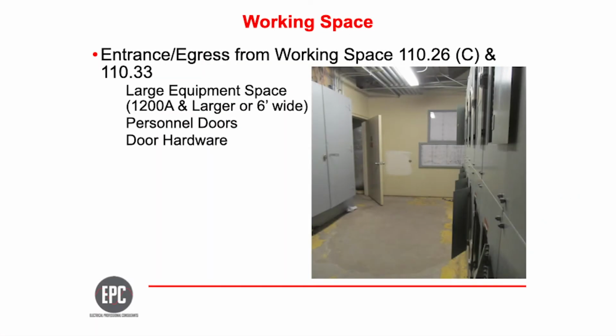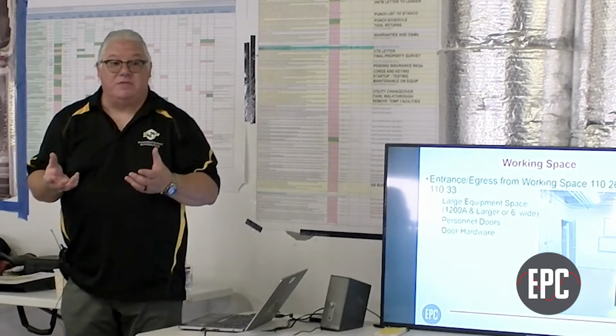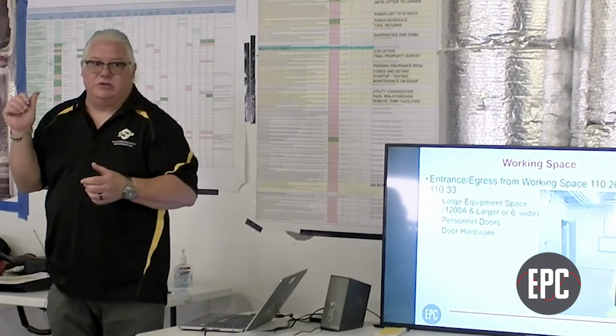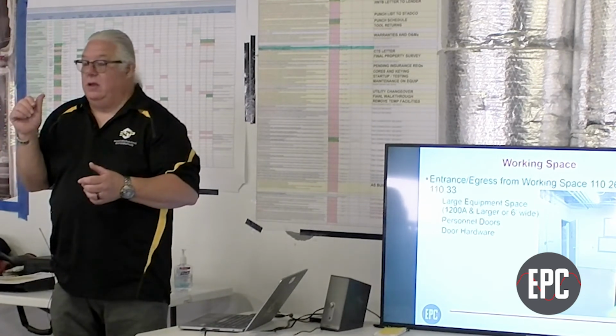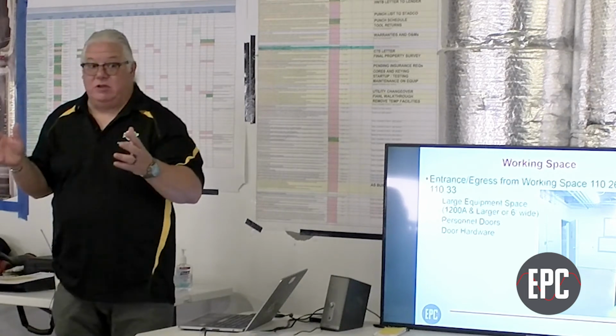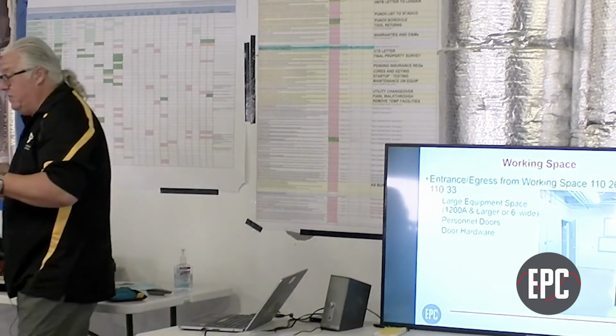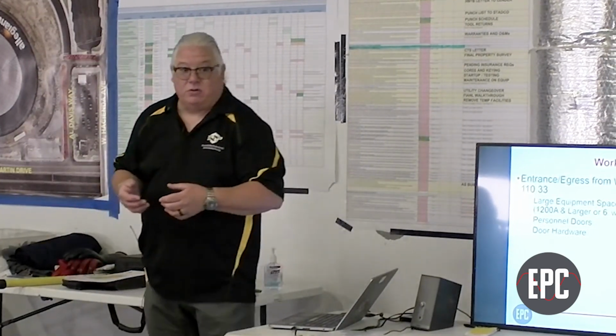We talked about egress from the room. What are some of the important things? You're in a brand new building that shouldn't have this problem, but if you're in an older facility, what are some of the important things that I want to understand about getting out of the room? Clear path, locks. I want to make sure that I can get out of the room. There's nothing worse than to walk into the electric room and hear the door shut behind you. If you've ever worked in some of the older facilities, the facilities that were built in the 60s and 70s, the doors open in.